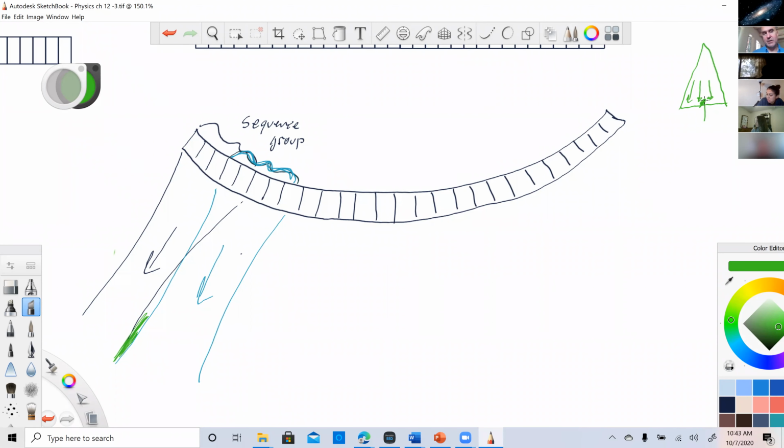Beam focusing can be done electronically. So let's go back to this blue one. 1, 1, 2, 2, 3. So we create a wave front. Let's say it was focused to this point. A little bit of a curve in that wave front forces that beam to narrow. And then, by the way, I know I've told you this before, afterwards, the waves actually inflect and then they'll spread out forever. They'll never come back together again.